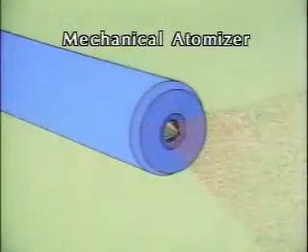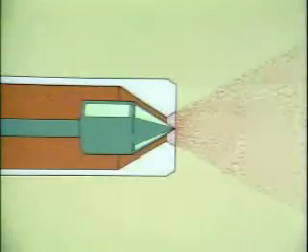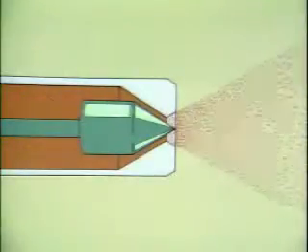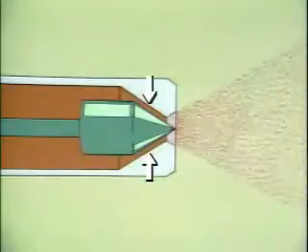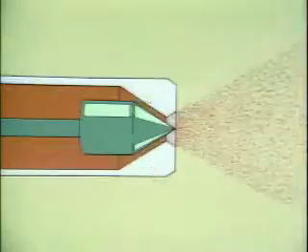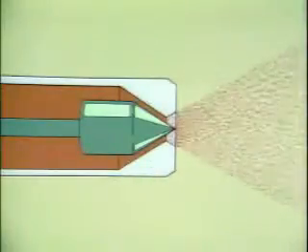A mechanical atomizer depends on the pressure of oil passing through a nozzle to produce a fine mist. Fuel entering the atomizer flows to a sprayer head; the oil is forced through the nozzle, which breaks it into droplets. The droplets are then sprayed into the combustion area in the form of a fine mist.